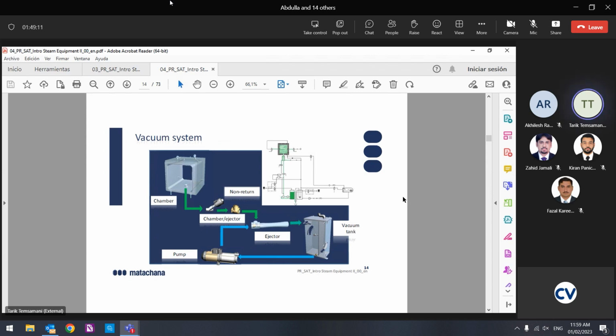Actually, is the valve repairable? Actually, I repaired it in the past. There is a Teflon and a key washer only. So we need to open it, and if we can get a part made by a machinist in the local market, for the time being we can repair it, but it will not be efficient as per the manufacturer. Normally we change some gasket and something inside the pump, but it gives you more work and more time than changing the valve. There's not a big difference between the kit and the valve. Okay, but you can repair it.